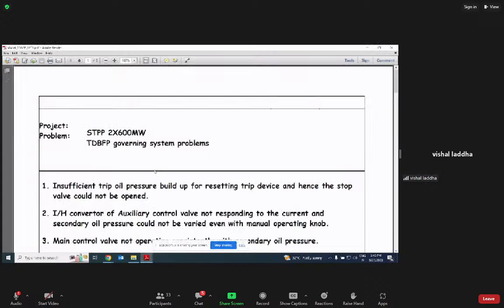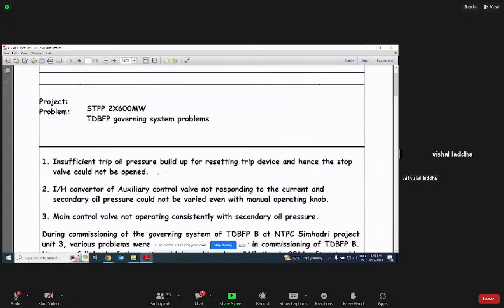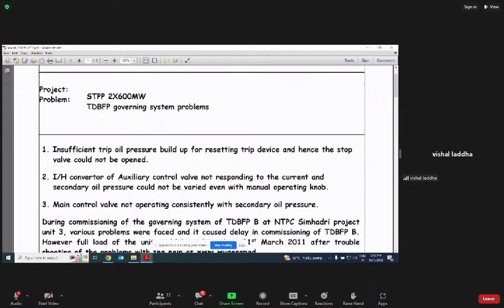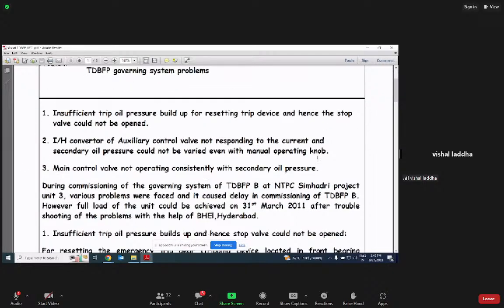Now I will show you the TDBFP case study. TDBFP also has some governing principle, and in TDBFP we faced some problems. Insufficient trip pressure build up for resetting the trip device, and hence the stop valve could not be opened. I/H, meaning current to hydraulic converter of the auxiliary control valve, not responding to the current, and secondary oil pressure could not be varied even with the manual operating knob. Main control valve not operating consistently with secondary. These all three things we observed.